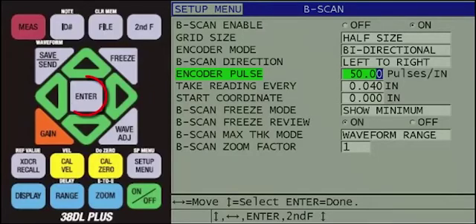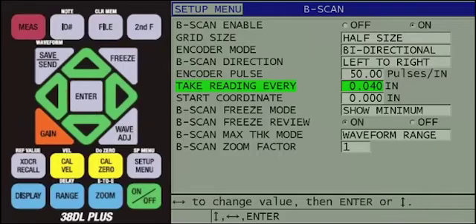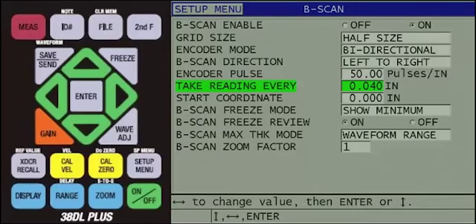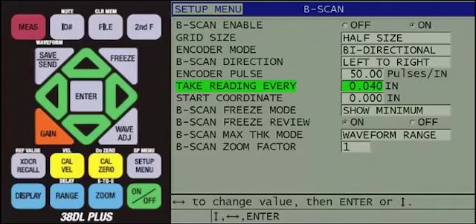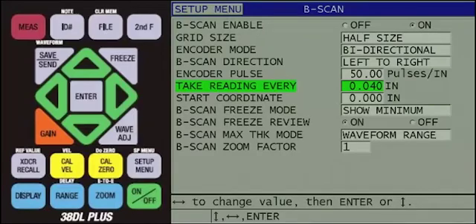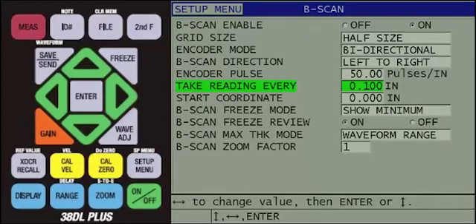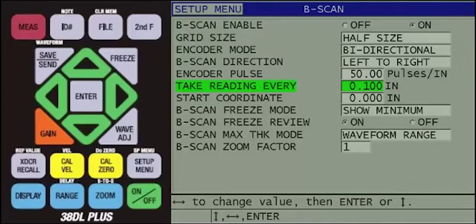Then, press the Enter key to highlight Take Reading Every. As discussed in previous slides, having the instrument make measurements every 0.040 inches, 1 millimeter, will require the user to move the buggy quite slow, since the gauge needs to take a reading every 0.040 inches, or 1 millimeter. For this demo, we will change this setting to 0.100 inches, 2.54 millimeters, by pressing the right arrow. This allows us to move the buggy at a more natural speed, while still having good scanning resolution while inspecting the sample.